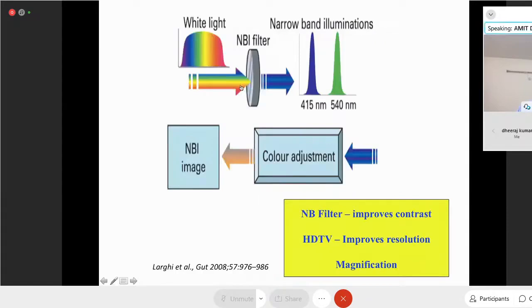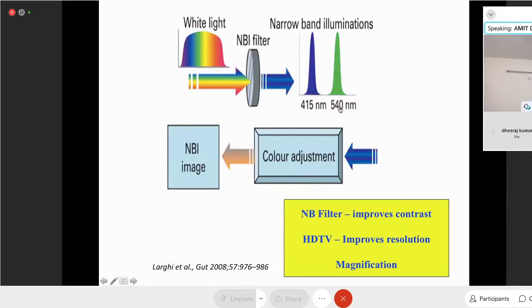The NBI endoscope looks similar to a white light endoscope. The main difference is the NBI filter. When you press the narrowband imaging button, the NBI filter comes into the pathway of white light, filtering it to give only a small wavelength of blue at 415 nm and green at 540 nm. These wavelengths illuminate the mucosal surface, adding contrast to the image. Combined with high definition television for more resolution and magnification, the final image benefits from narrowband contrast, HD resolution, and magnification.